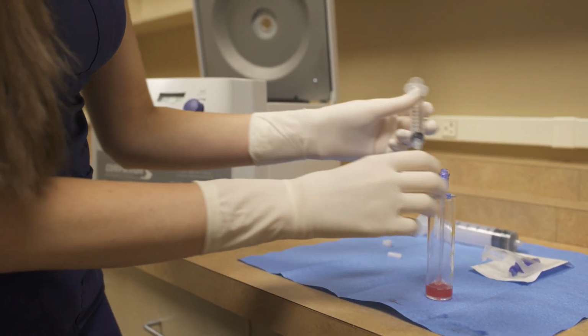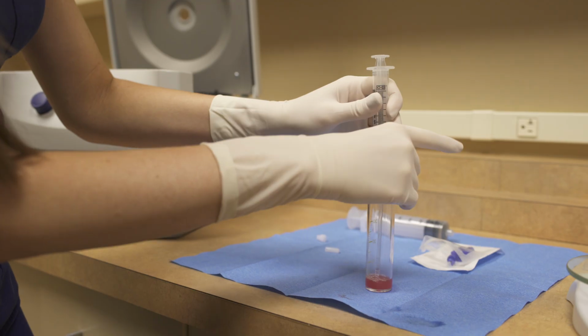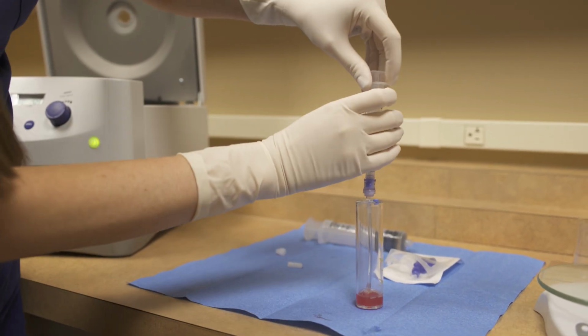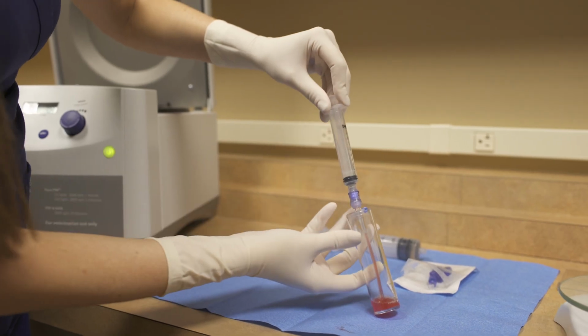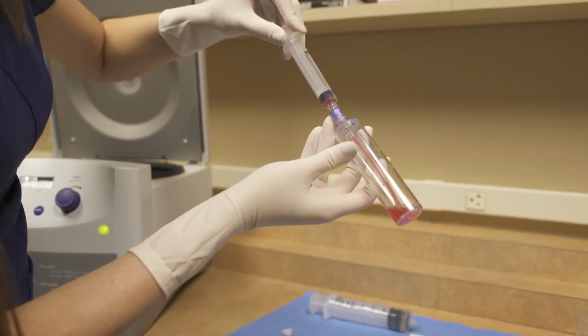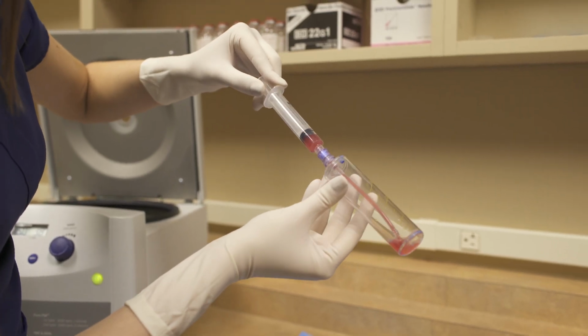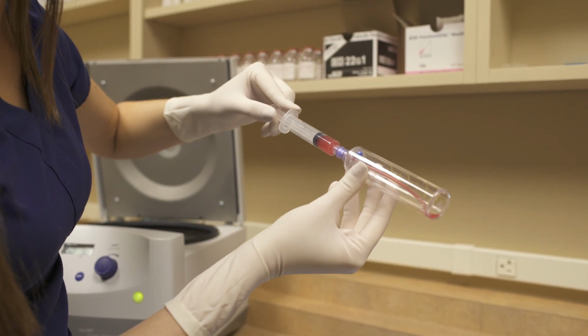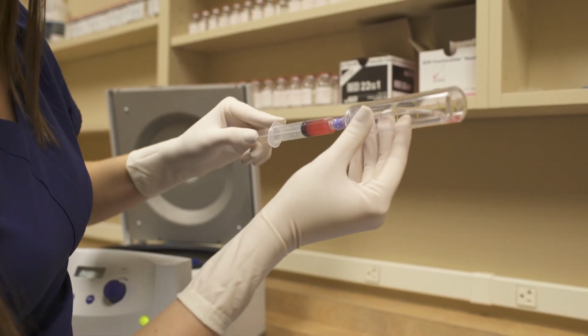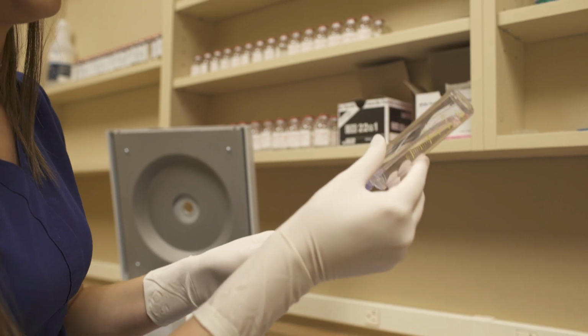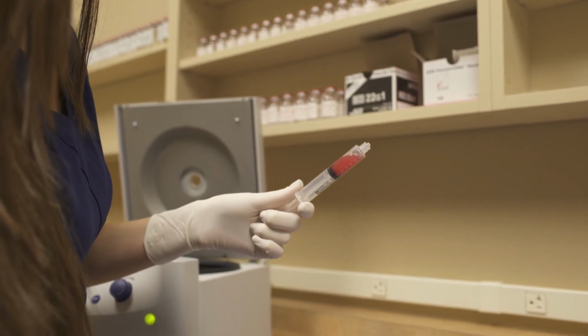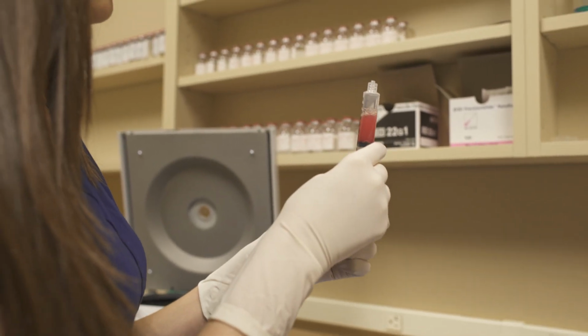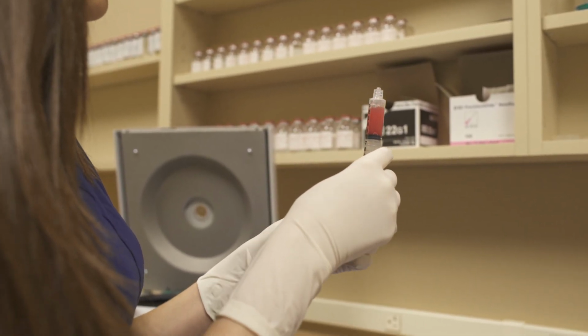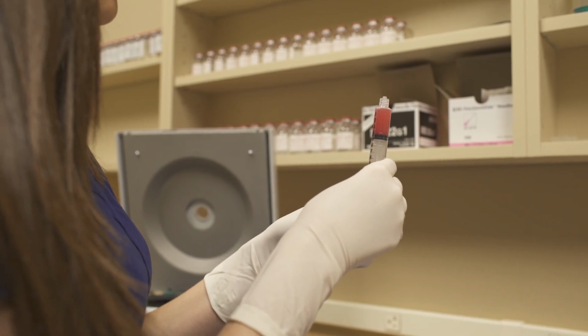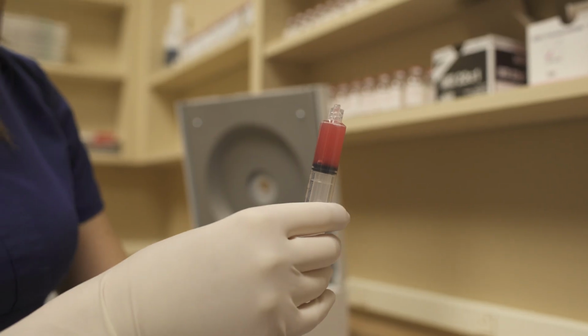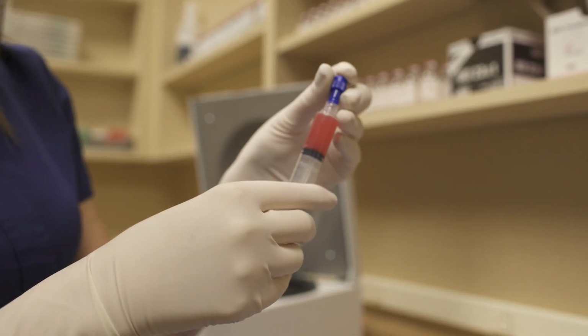Once a uniform cell suspension has been reached, attach the 10 milliliter syringe to the device. Tilt the device to immerse the aspirating pipe into the pure PRP and gently draw back on the plunger of the syringe. Continue to tilt the device as the PRP is drawn until all of the suspension has been captured. Detach the syringe and remove any aspirated air. Place a syringe cap on the end of the syringe, and your pure PRP is ready for use.